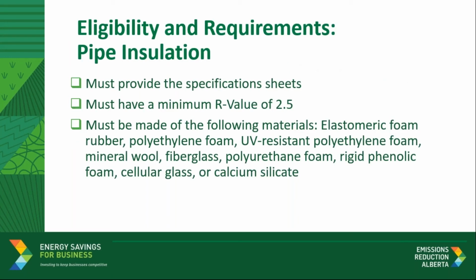So when you're applying, you must provide the specification sheet and ensure that the pipe insulation has a minimum R value of 2.5. The pipe insulation must also be made of any of the following materials. So there could be elastomeric foam, rubber, polyethylene foam, UV resistant polyethylene foam, mineral wool, fiberglass, polyurethane foam, rigid phenolic foam, cellular glass, or calcium silicate.